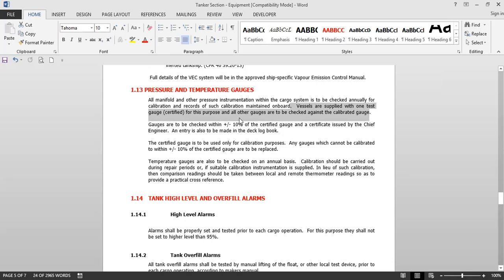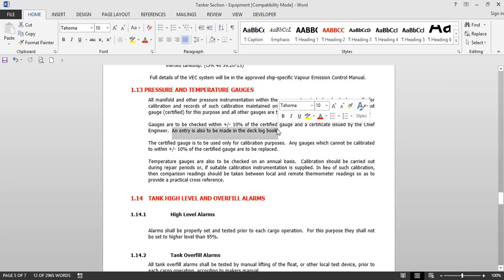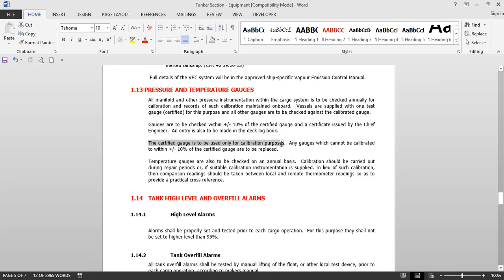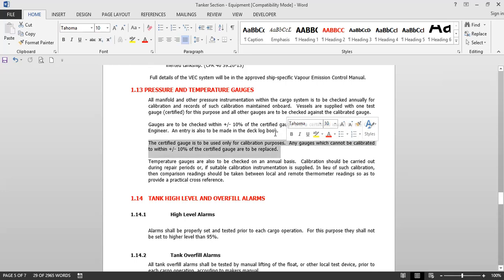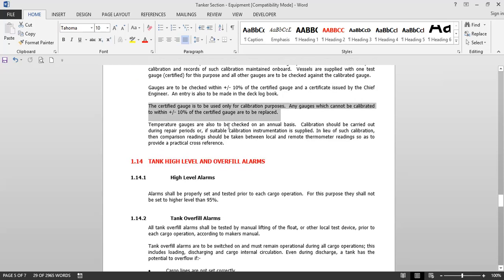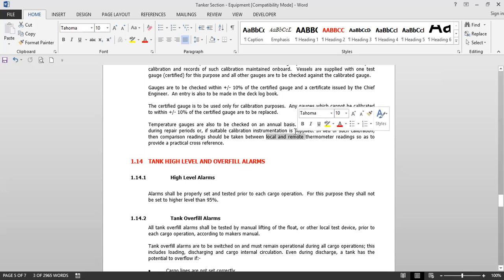An entry is also to be made in the deck log book that the pressure gauges have been tested. Any gauges which cannot be calibrated to within plus or minus 10 percent of the certified gauge are to be replaced. Temperature gauges are also to be checked on an annual basis. Calibration should be carried out during repair periods or, if suitable calibration instrumentation is supplied, comparison readings should be taken between local and remote thermometer readings to provide a practical cross reference.